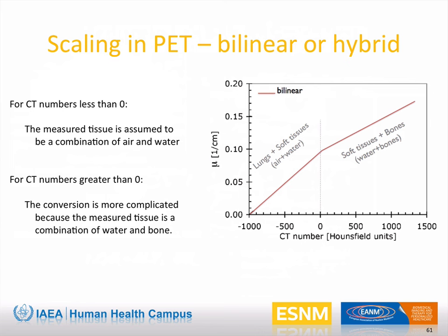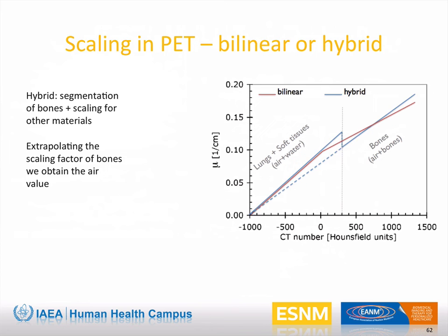Conversion coefficients and threshold values are usually suggested by the scanner manufacturer. Some more complex scalings are also sometimes used, but are all based on some form of linear conversion. The linear scaling approximation fails in the presence of high-Z materials that cannot be approximated as a mixture of air, water, and bone.